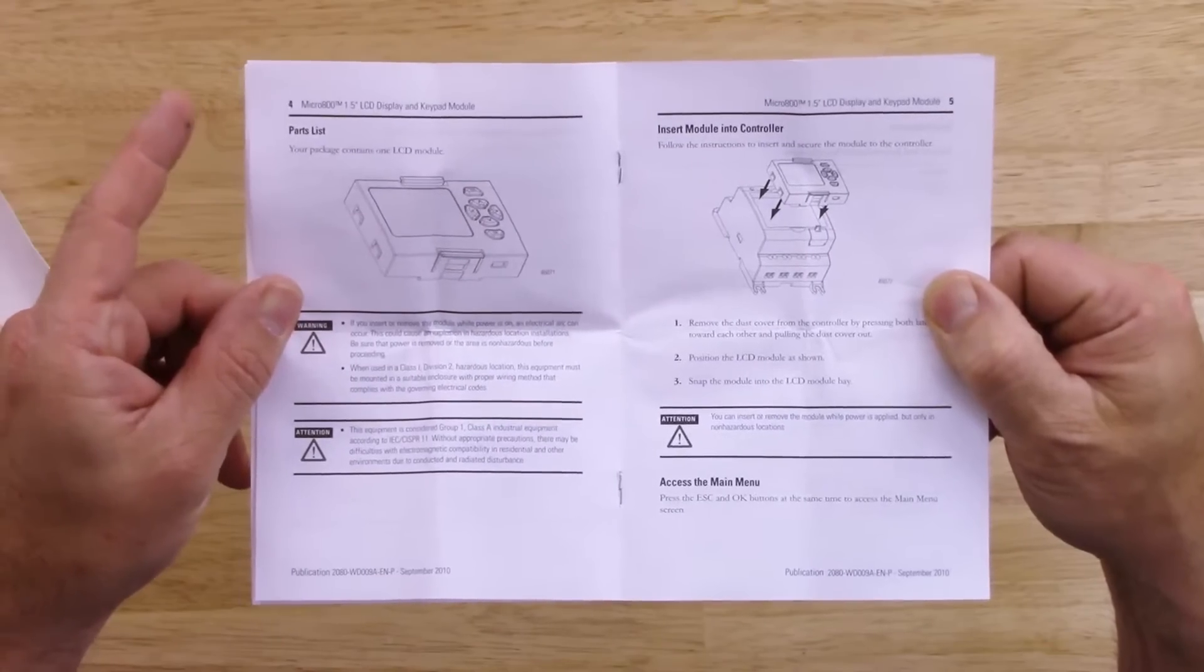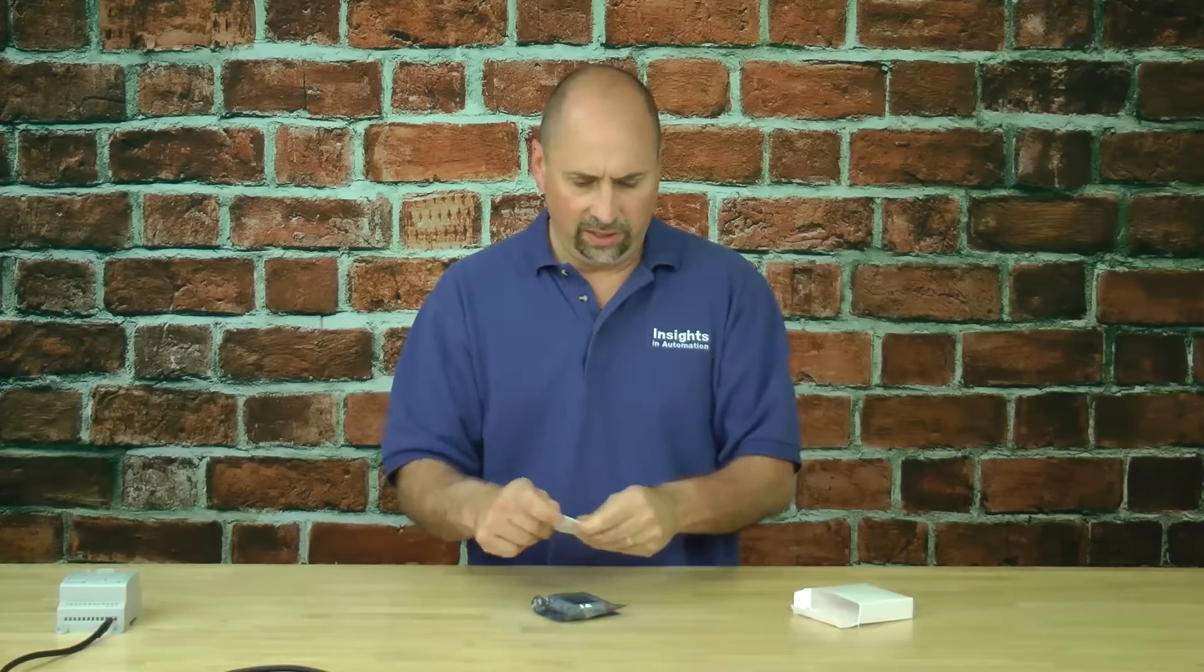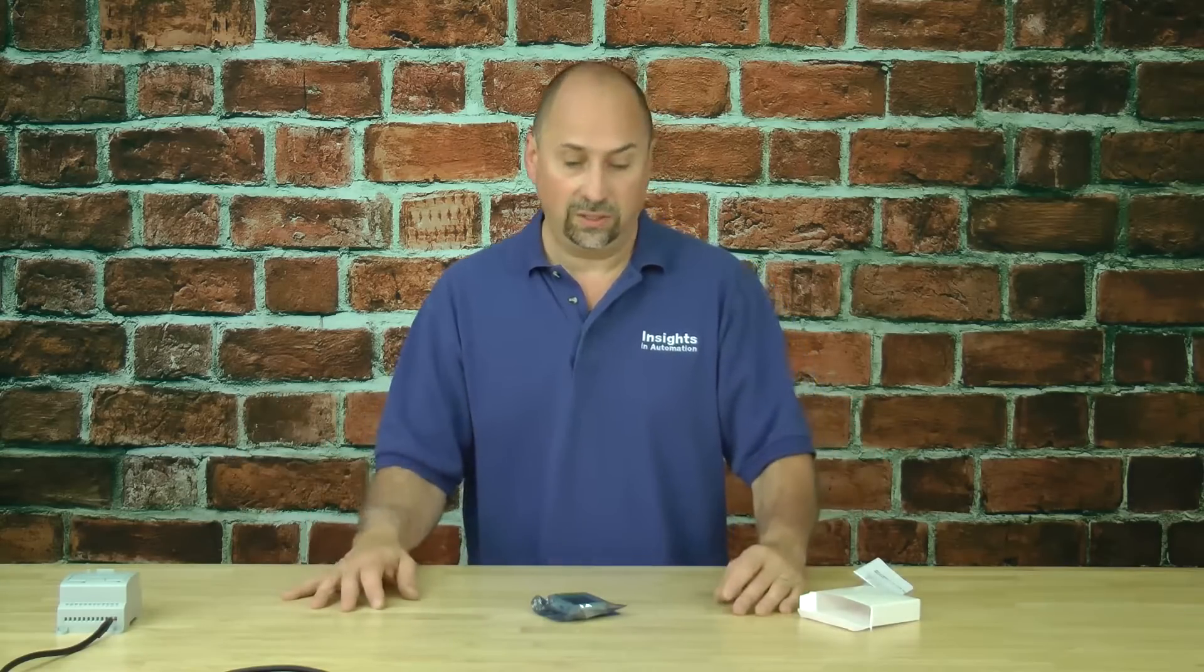We'll go ahead and plug ours in with power off anyways, but the only thing it does say in there is that if you're in a Class 1, Div 2, kind of hazardous location, you don't want to be unplugging and plugging this in because you can get arcs, and arcs can cause an explosion if there's explosive gases around.